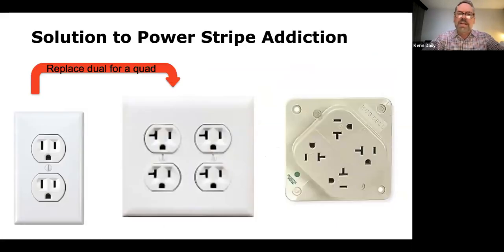What you really need to be doing is going from a dual plug to a quad plug or even bigger. I've seen 6 and 8 receptacles, but the whole point is that you're going to be increasing the number of wall receptacles at your facility behind the resident bed, even in offices. That one on the far right is where you would wire in, and then there's a plate, then the four receptacles. That's where some of you have concrete block walls, so you can't cut in very easily into your drywall around the concrete block. So you do this on top. It leaves about 1.5 inches of height, but it's a very good repair to add more receptacles. You're adding more receptacles to your building, which is perfect.